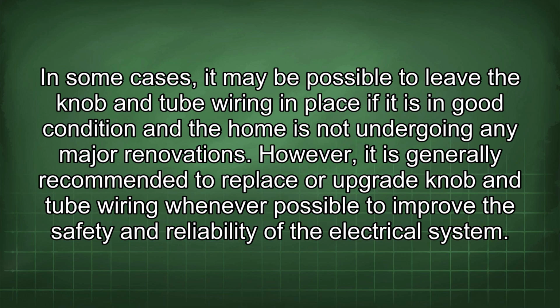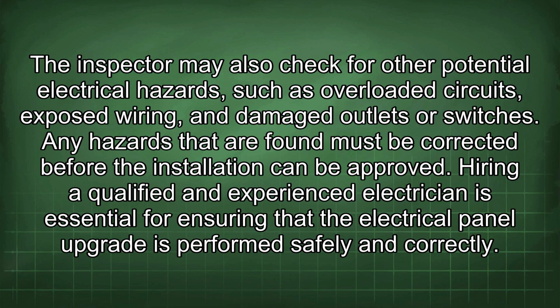In some cases, it may be possible to leave the knob and tube wiring in place if it is in good condition and the home is not undergoing any major renovations. However, it is generally recommended to replace or upgrade knob and tube wiring whenever possible to improve the safety and reliability of the electrical system. The inspector may also check for other potential electrical hazards such as overloaded circuits, exposed wiring, and damaged outlets or switches. Any hazards that are found must be corrected before the installation can be approved.